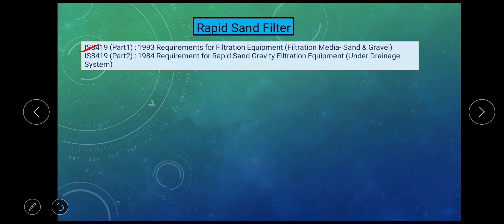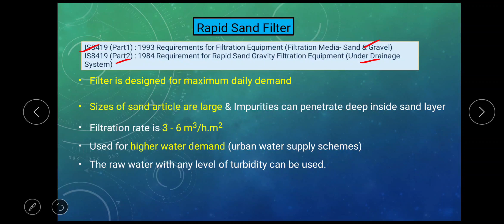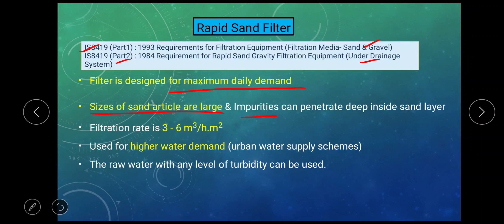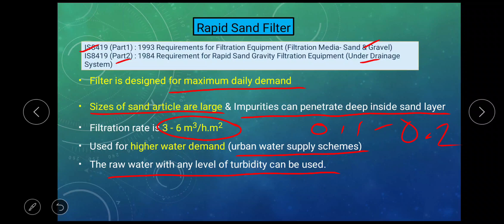As per Indian Standard 8419 Part 1, it tells us about filtering media of rapid sand filter. Part 2 tells us about the under drainage system of rapid sand filter. The filter is designed for maximum daily demand. The size of the sand particles are large, so impurities may penetrate deep inside the sand layer. Filtration rate of rapid sand filter may vary from 3 to 6 meter cube per hour per square meter. Rapid sand filter is generally used for urban water supply schemes where we have high water demand. The raw water with any level of turbidity can be used.